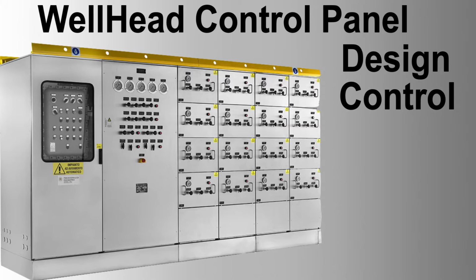well requirements. Key functions. 1. Valve control. Operates surface and subsurface safety valves, SCSSV, SSSV, choke valves, and other wellhead valves. 2. Pressure monitoring. Monitors annulus pressure, tubing pressure, and other critical pressure points. 3. Emergency shutdown, ESD. Provides automated shutdown capabilities in case of abnormal conditions to ensure safety.